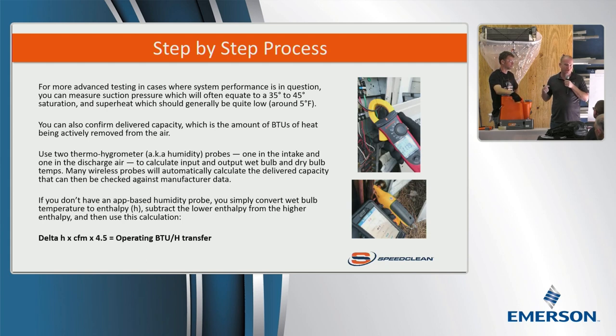But once you look at the chart and you know the airflow, that's all you need. Two sensors, airflow measurement from the manufacturer. It'll tell you what BTUs you're producing, as long as your sensors are working right. So that's it. That's how you do it.